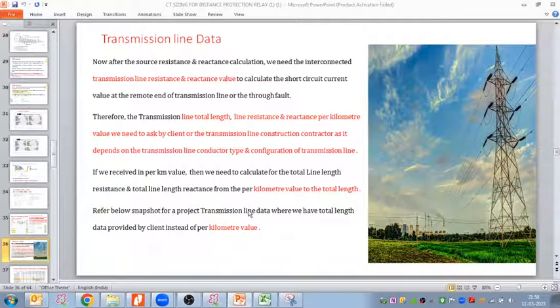Okay, thank you all. Now, once the source resistance and reactance calculations are done, because we are not aware how many plants and transmission substations are coming, or where the generator plant is located, I am taking the reference of fault current. If we have a 63 kiloampere fault current at 220 kilovolts, then for that voltage and that fault current, how much impedance will it offer? Through that we calculate the source resistance and reactance.